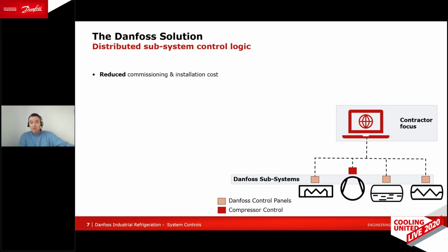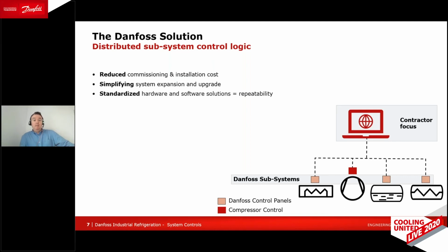So these products we're bringing to market, I'll give you a few headlines. We believe it's going to reduce commissioning and installation cost, because there's reduced need for the PLC guy. He can concentrate more on the supervisory PLC and doesn't have to go out and program the logic for the evaporators and so on, so he can focus on more central tasks. We also believe it won't be essential to access the PLC code in order to expand an existing system. These pre-programmed solutions will make expansion of a system quite a bit easier.